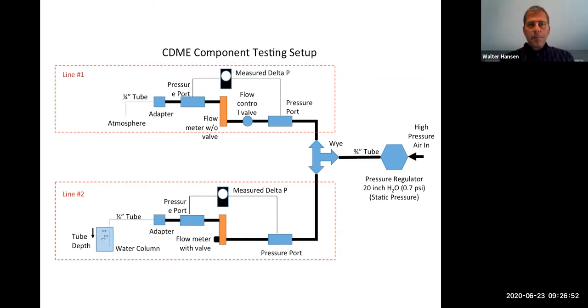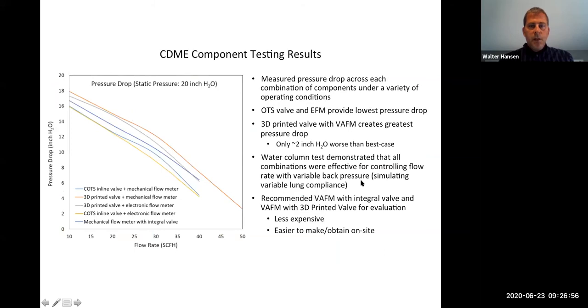So here is a summary of our test results. The major takeaway was that we were able to control flow rate in each line independently, and that the difference in pressure drop between the worst and best combinations was only about 2 inches of water, which is low enough that the pressure drop is roughly equal for all combinations we tested.